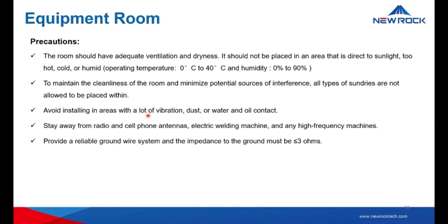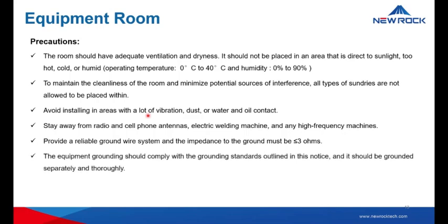Then we need to provide a reliable ground wire system. The impedance of the ground must be less than or equal to 3 ohms. The equipment grounding should comply with the grounding standards. We have the grounding rules later on, and it should be grounded separately and thoroughly.